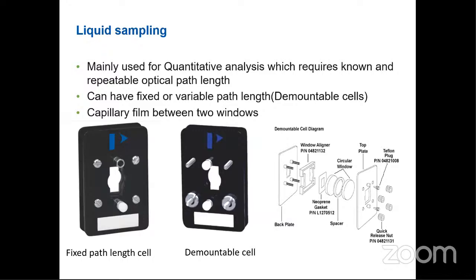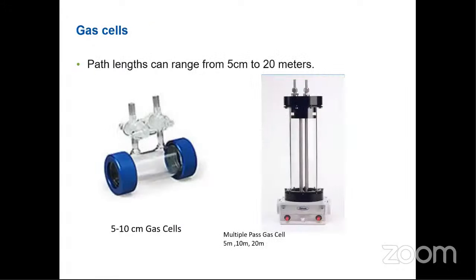Liquid sampling is mainly used for quantitative analysis and requires a known and repeatable optical path length. It can have a fixed or variable path length, with a capillary film between two windows. So we fill the liquid material in the demountable cell and check it. For gas cells, there are two different types. One is a smaller gas cell, 5 to 10 centimeters, and the other is a bigger gas cell, with a path length of 5 meters, 10 meters, and 20 meters.